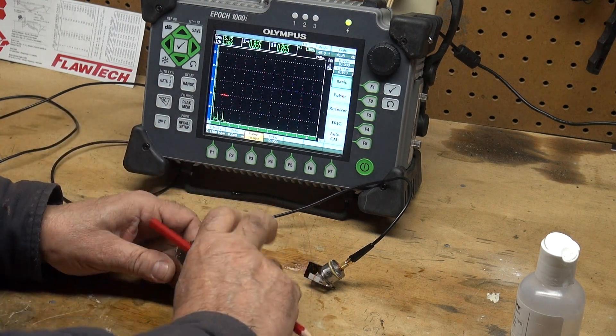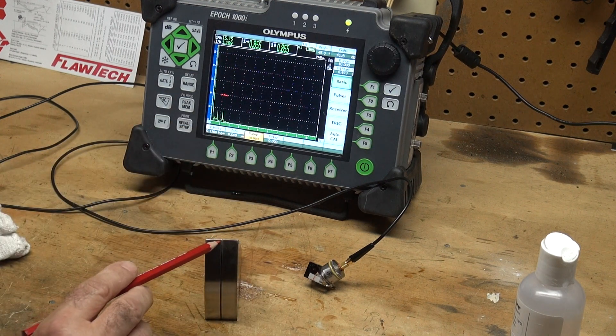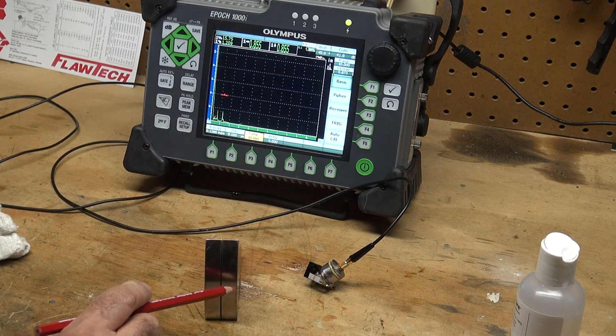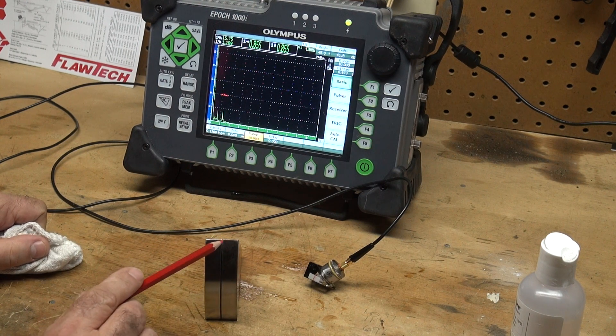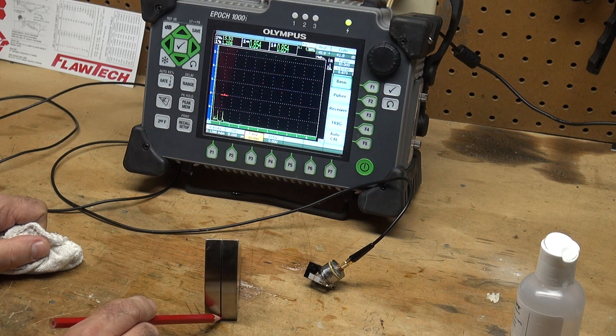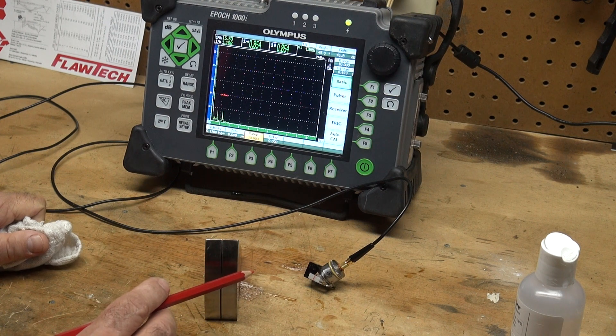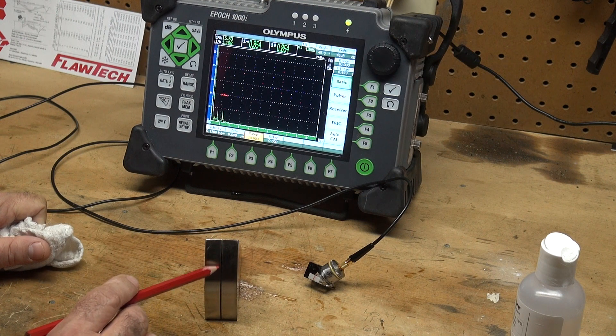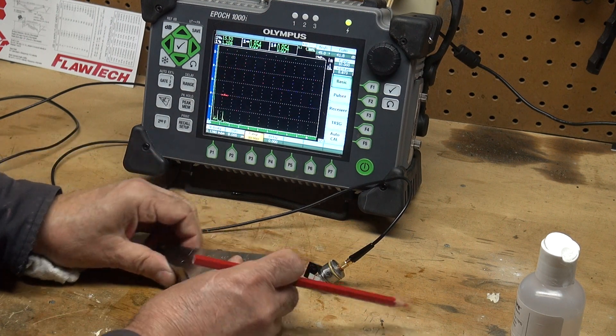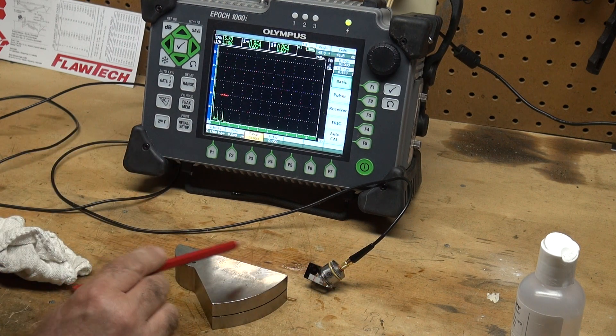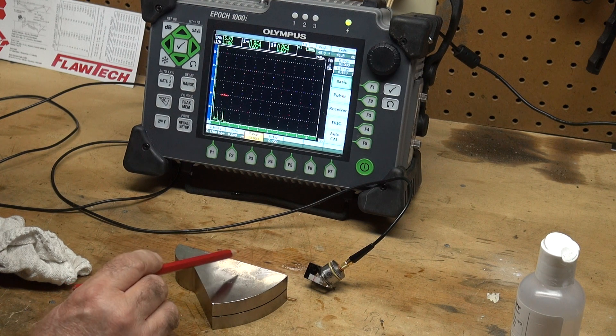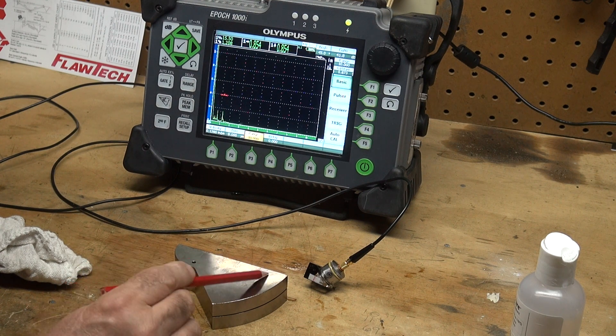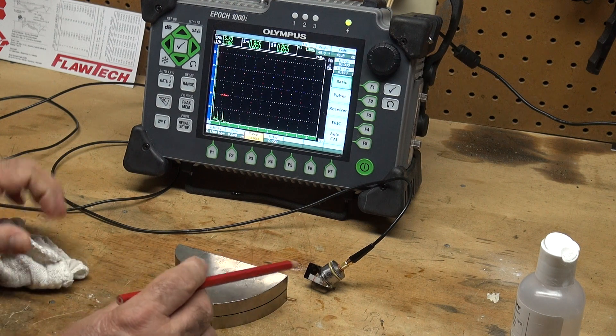Another thing that's interesting about this block is that on the edge with the three-inch radius, there is a 1/32-inch wide groove that is cut at 0.375 inches deep, and we use that for our reference. Also, I can measure the angle of my transducer shooting at this hole, and it's 45 to 70, looks like 75 degrees scale here.